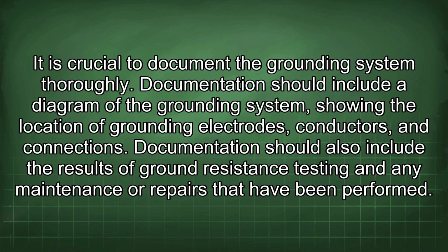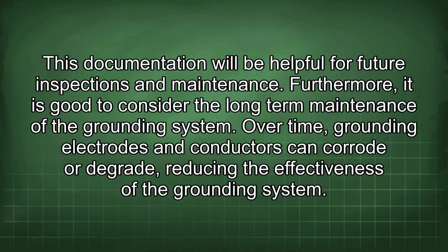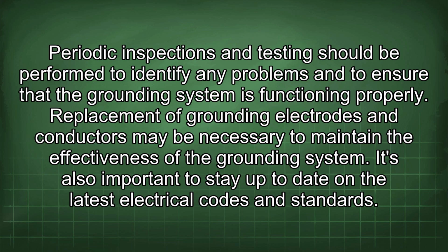It is crucial to document the grounding system thoroughly. Documentation should include a diagram of the grounding system showing the location of grounding electrodes, conductors, and connections. Documentation should also include the results of ground resistance testing and any maintenance or repairs that have been performed. This documentation will be helpful for future inspections and maintenance. Furthermore, it is good to consider the long-term maintenance of the grounding system. Over time, grounding electrodes and conductors can corrode or degrade, reducing the effectiveness of the grounding system. Periodic inspections and testing should be performed to identify any problems and to ensure that the grounding system is functioning properly. Replacement of grounding electrodes and conductors may be necessary to maintain the effectiveness of the grounding system.